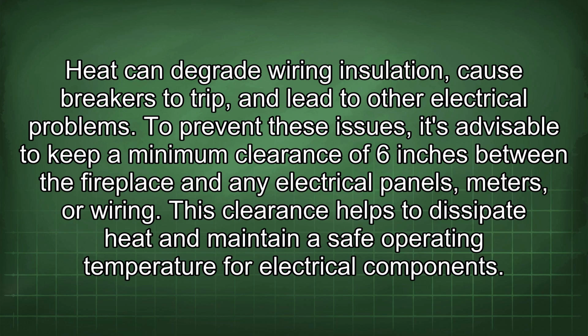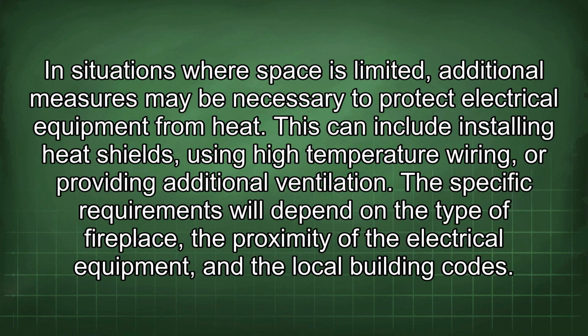Heat can degrade wiring insulation, cause breakers to trip, and lead to other electrical problems. To prevent these issues, it's advisable to keep a minimum clearance of 6 inches between the fireplace and any electrical panels, meters, or wiring. This clearance helps to dissipate heat and maintain a safe operating temperature for electrical components. In situations where space is limited, additional measures may be necessary to protect electrical equipment from heat. This can include installing heat shields, using high-temperature wiring, or providing additional ventilation.